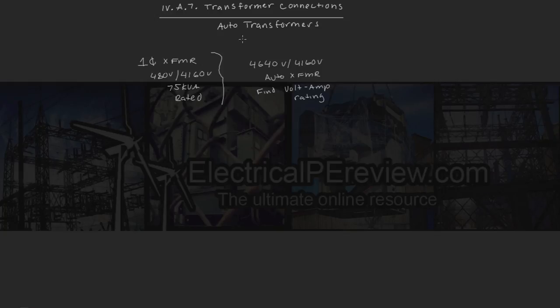In this episode, we're going to be doing an example of autotransformers from single-phase transformers. So say you work at a facility and you've got a slightly high voltage of 4640 and you've got an equipment rated voltage for 4160, and all you have laying around is a 480 volt to 4160 volt transformer. That's 75 kVA rated. Could you use this single-phase transformer to make a step-down autotransformer in order to regulate your voltage to where it needs to be to match the equipment rating of 4160? The answer, of course, is yes.